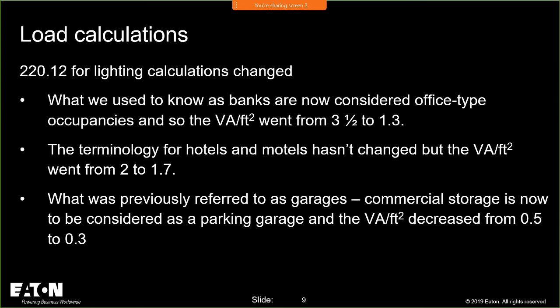So you're going to see that in some of the cases we did, if you're a bank guy and you do banks all day and you go to 220.12 and you don't see banks anymore, you have to know that now they're considered an office type occupancy. So we sort of went through that logic saying, well, what would be different in a bank that you wouldn't see in a general office? Other than a big old safe with probably a big lock on it, motor driven probably, it's pretty much the same, especially from a lighting perspective.